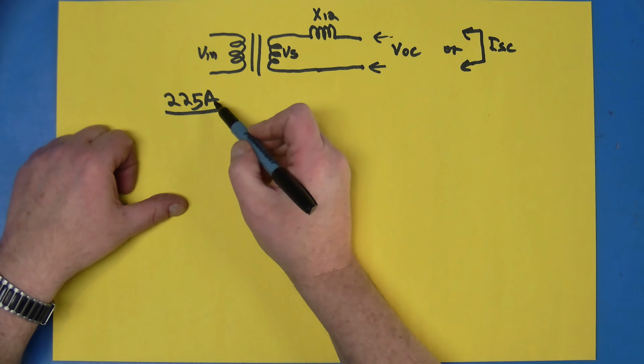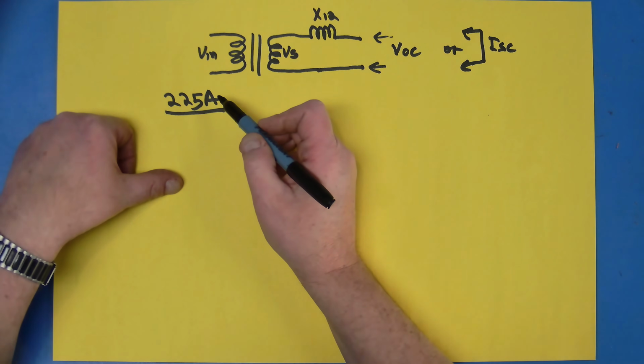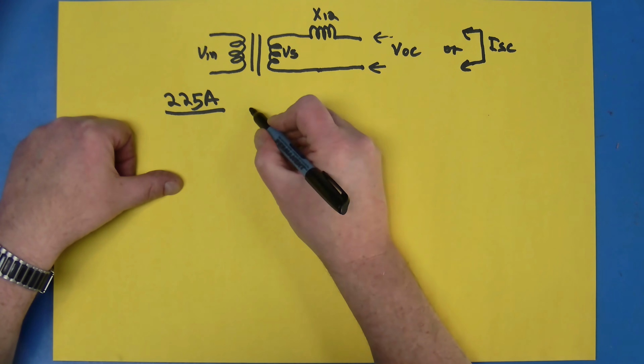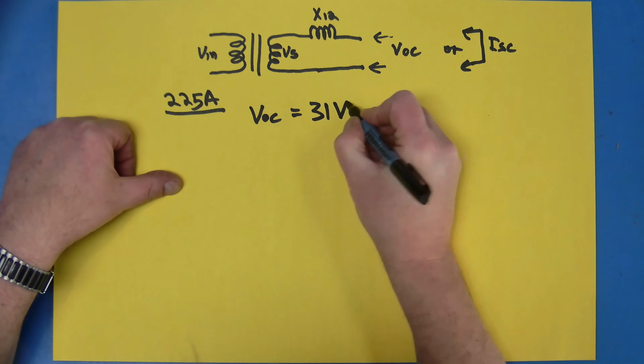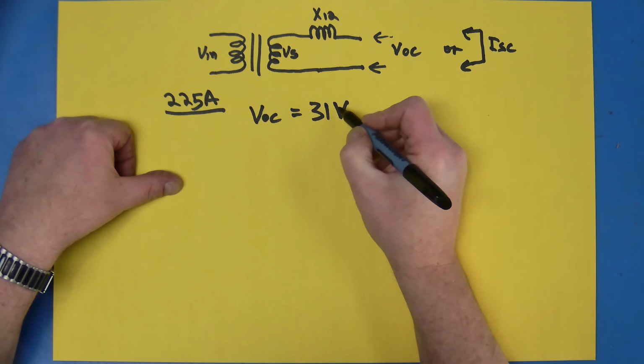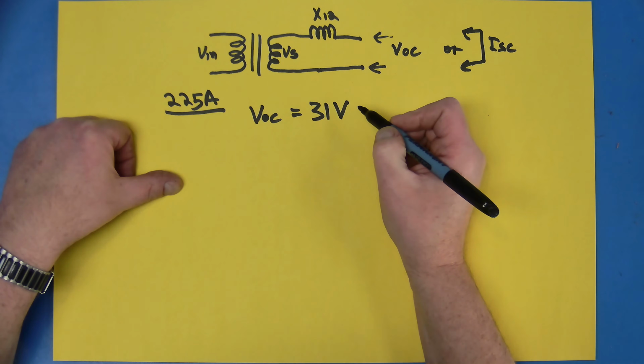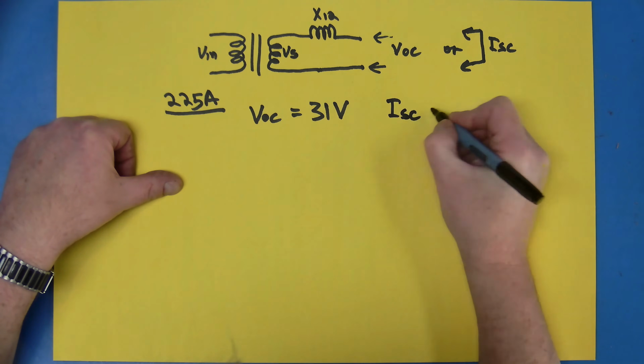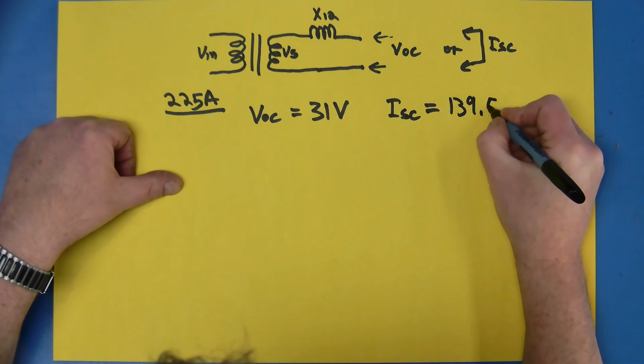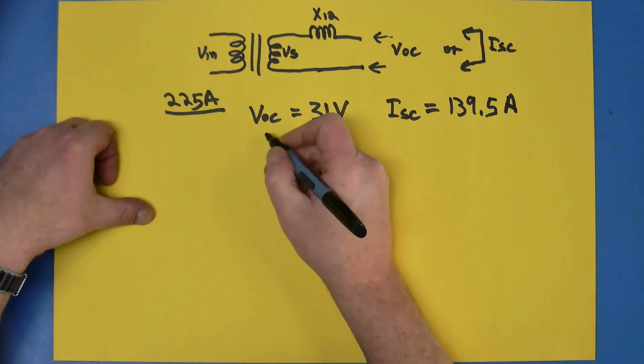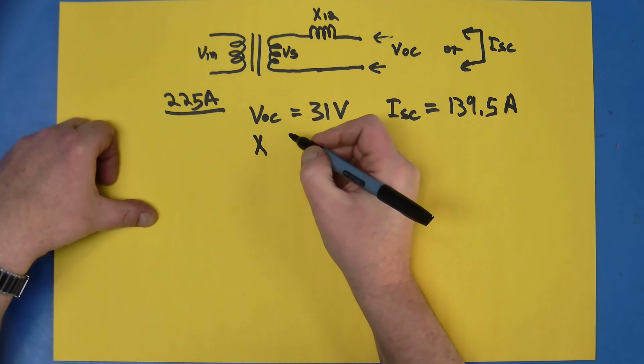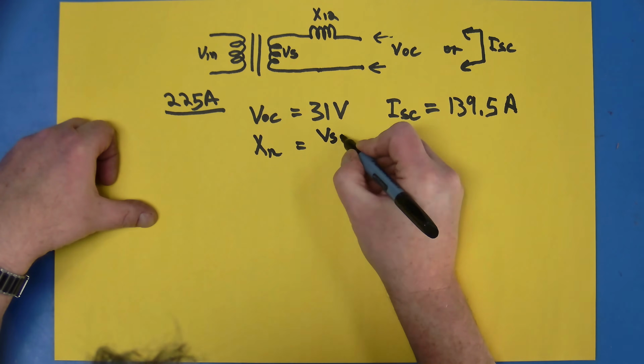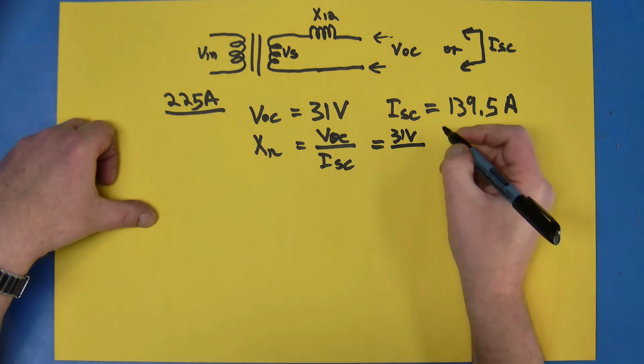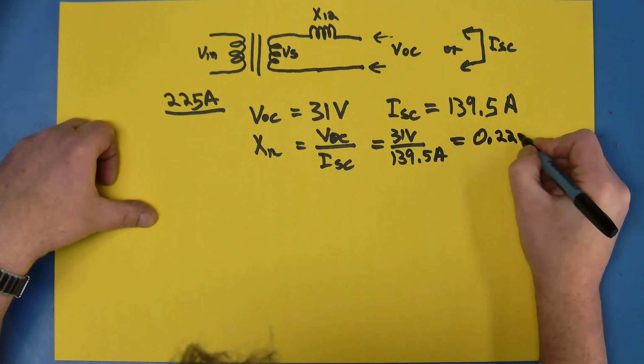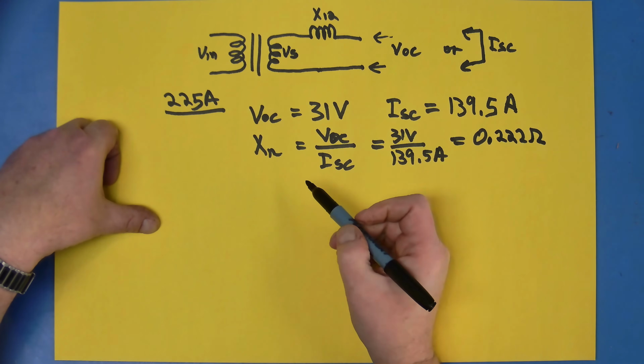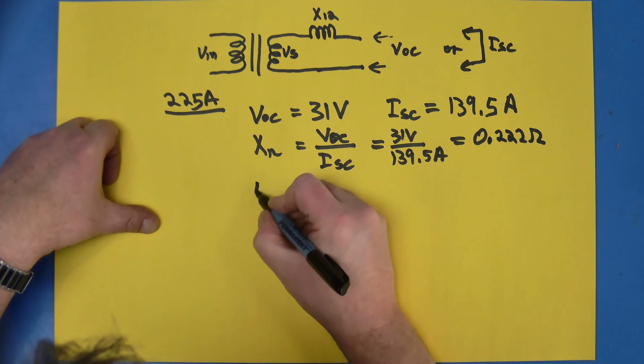For the 225 amp setting on our adjustable magnetic shunt, what did we get? We got a VOC equal to 31 volts, with 120 volts in, so we'd expect double, or 62 volts, if we had it at the normal 240 volts in. We also got a short circuit current of 139.5 amps. The reactance is equal to the voltage over the current, and that turns out to be 0.222 ohms.